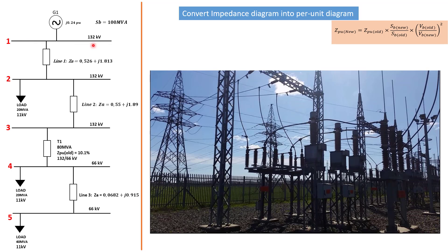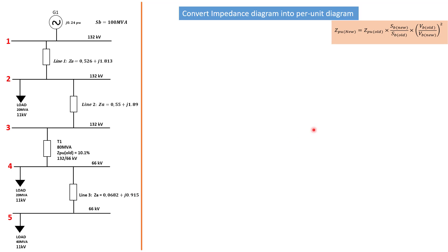We want to know the magnitude of the short circuit current on bus bar 1, bus bar 2, bus bar 3, bus bar 4 and 5. That way we will be able to work out the type of protection that we need for each bus bar and the device that needs to be selected in terms of current transformer, circuit breaker and so forth. Let's dive into it and see how we're going to get these per unit values.